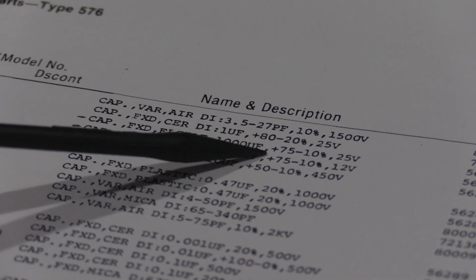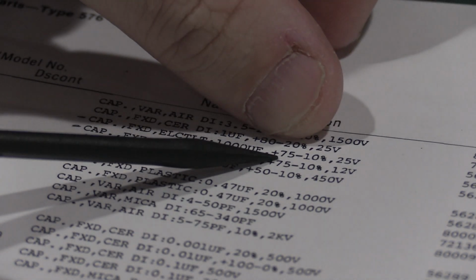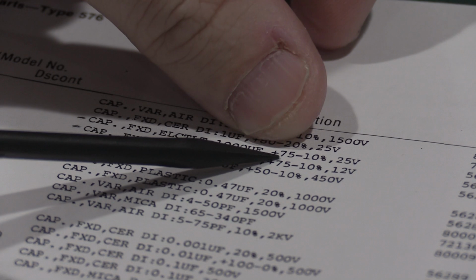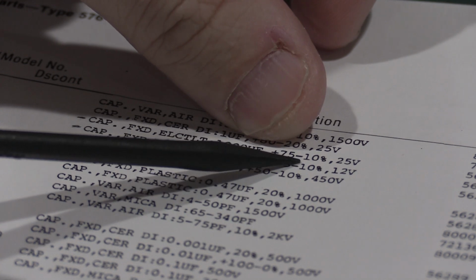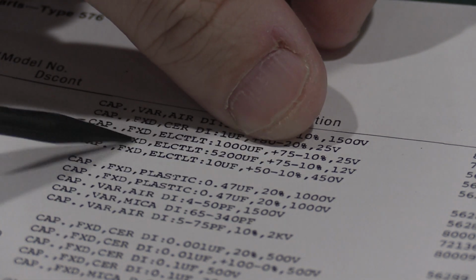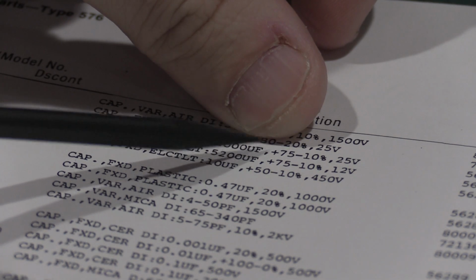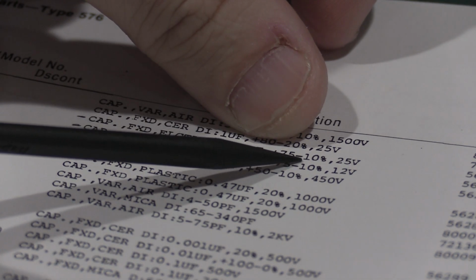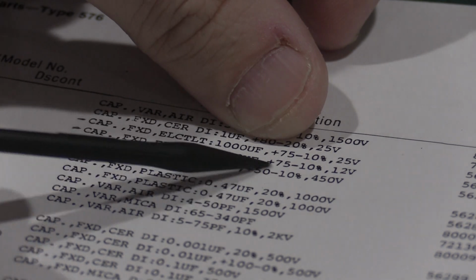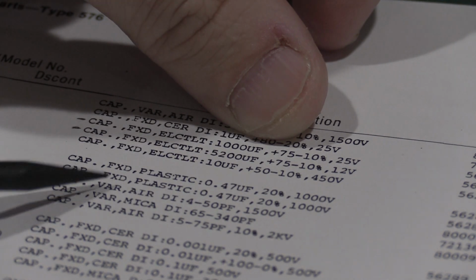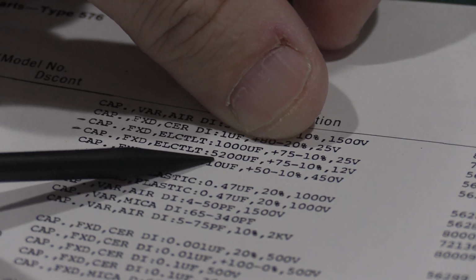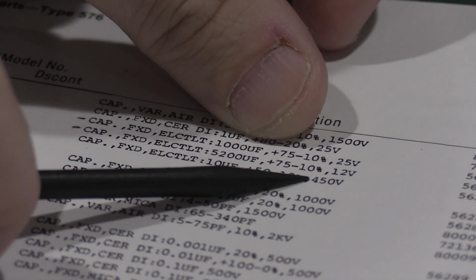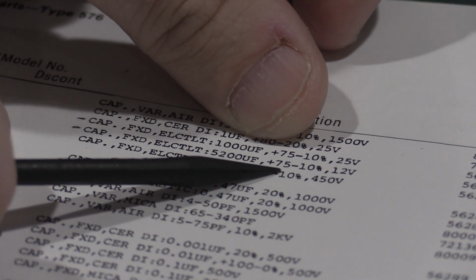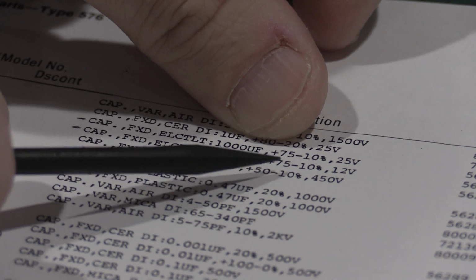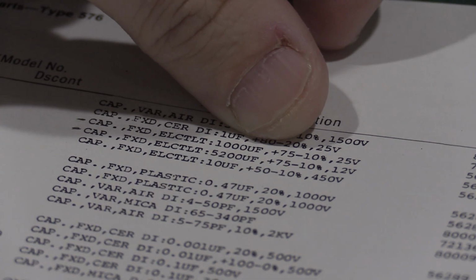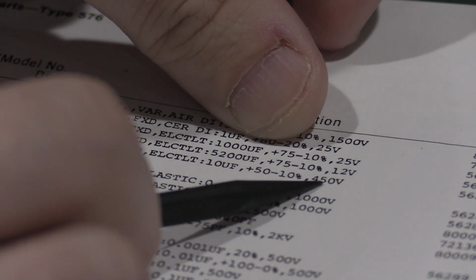One thing you'll notice is the tolerance of the capacitor is plus 75%, minus 10%. This means the circuit can handle a lot higher capacitance, but you don't want to go much lower because you need at least 1000 microfarads. Same thing for this one, a 5200 microfarad capacitor, also plus 75 minus 10. So the tolerances on these capacitors are actually pretty huge compared to a modern capacitor, which is typically plus or minus 20%.